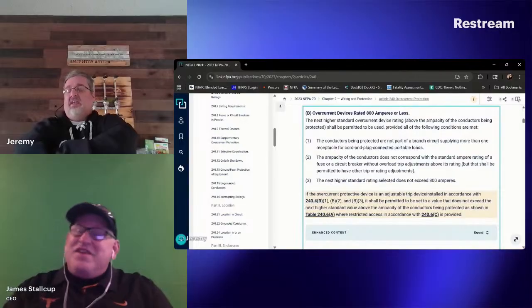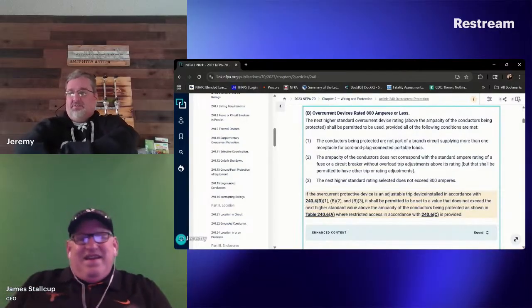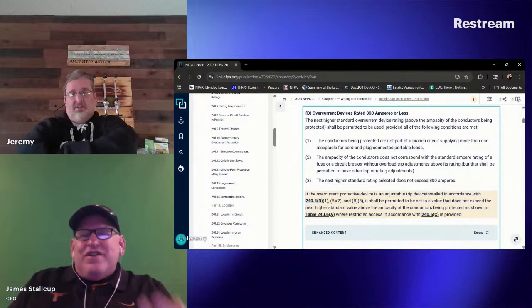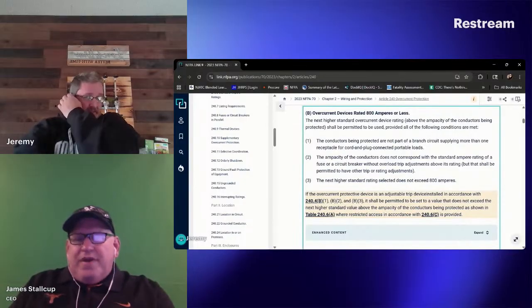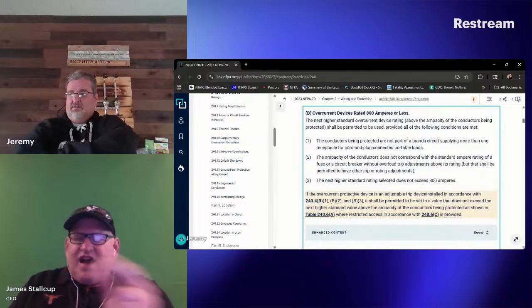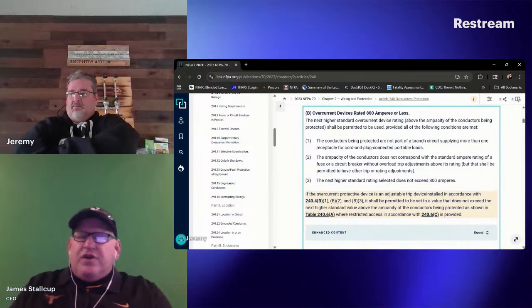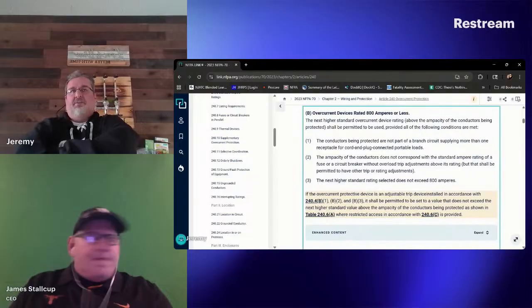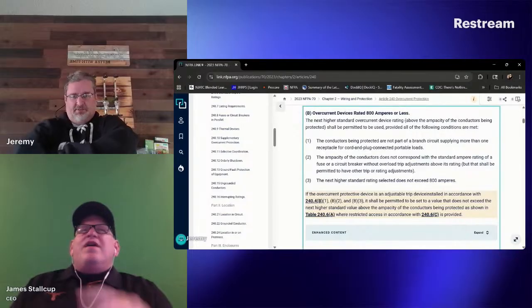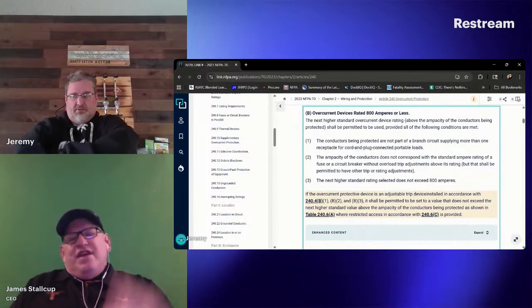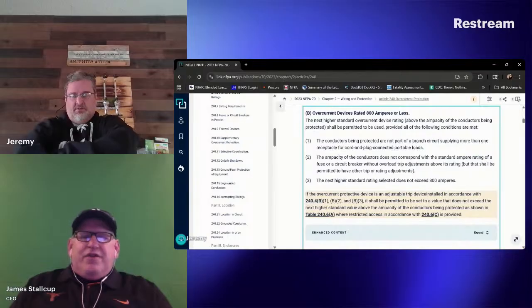Again, this is amazing. Where does it say anything about protecting a load in 240.4(B)? When you size your conductors and overcurrent devices, you do them exactly the same. And 240.4(B) tells you the rules and how to size the overcurrent protection device once those loads are calculated. It tells you how to protect the conductor. It doesn't tell you how to calculate a load. Show me anywhere in there where it's telling you that the size of the conductors has to be increased so I can get up to a size overcurrent device that meets your so-called 1,000 amps.